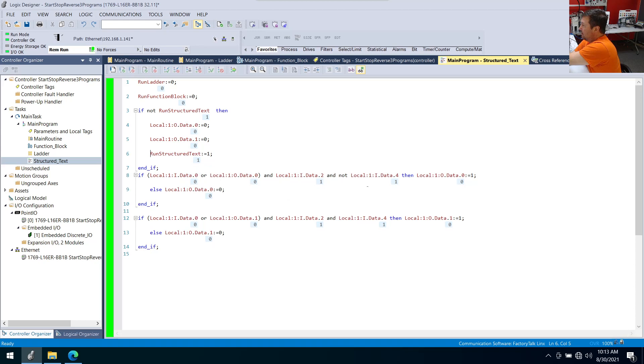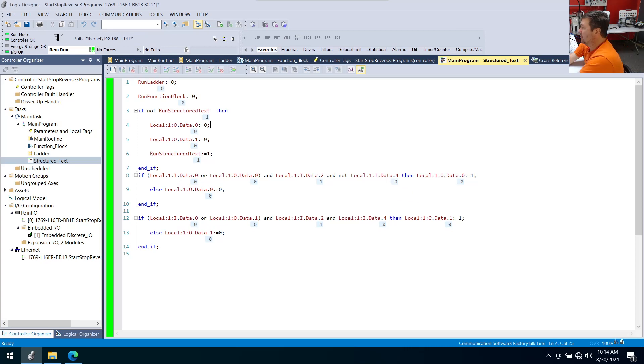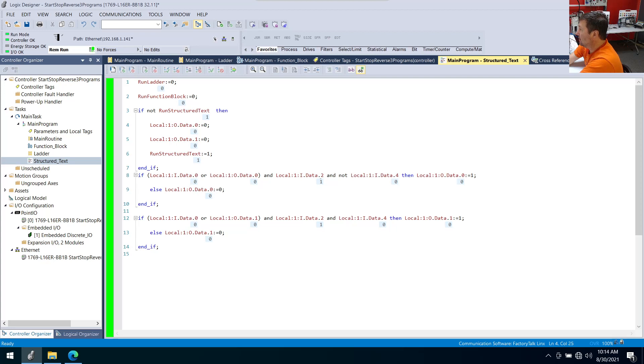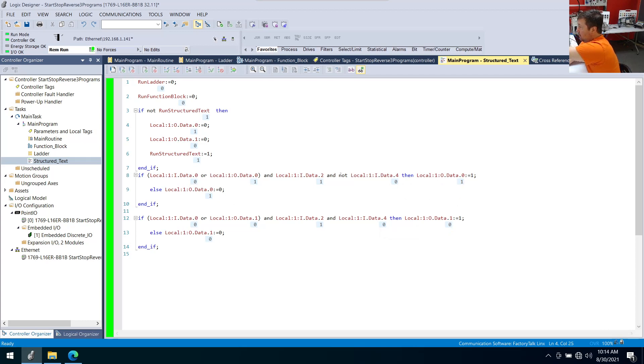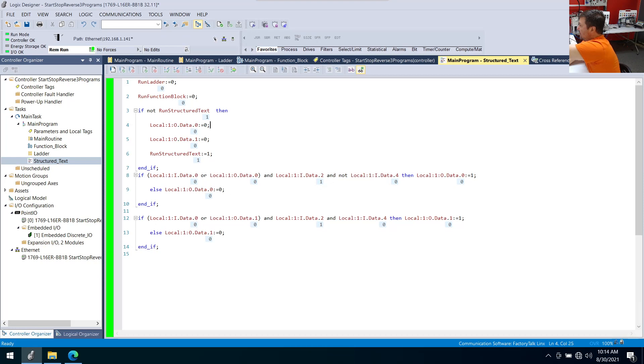I'm going to switch switch four here to the left position. Now we have a zero there and it's looking for a not. So Local colon one input zero, if it's a one, which is our green light, or if our motor is running, and we have a one in our red light, which means it's not pressed, and switch one is in the left position, then go write a one to the green light. And we're going to see that. There it goes. Else write a zero. So when I press the red button, this condition is not going to be satisfied anymore. And it writes a zero. So this does the exact same functionality as our function block and our ladder.